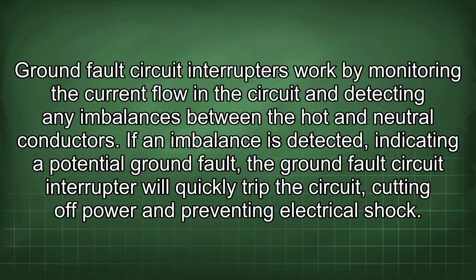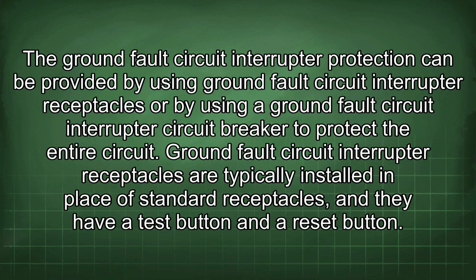Ground fault circuit interrupters work by monitoring the current flow in the circuit and detecting any imbalances between the hot and neutral conductors. If an imbalance is detected, indicating a potential ground fault, the ground fault circuit interrupter will quickly trip the circuit, cutting off power and preventing electrical shock. The ground fault circuit interrupter protection can be provided by using ground fault circuit interrupter receptacles or by using a ground fault circuit interrupter circuit breaker to protect the entire circuit.